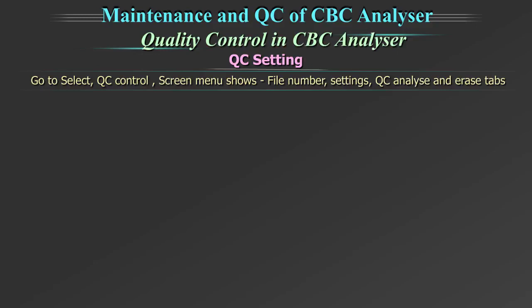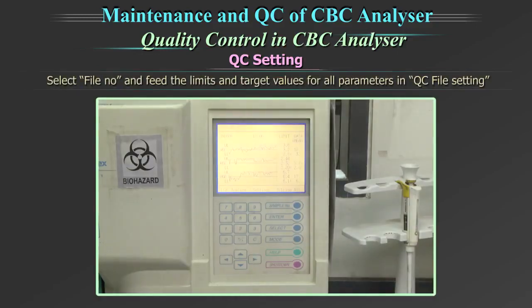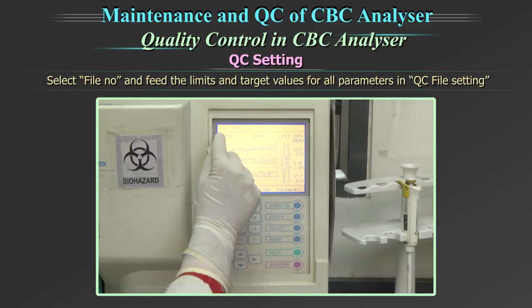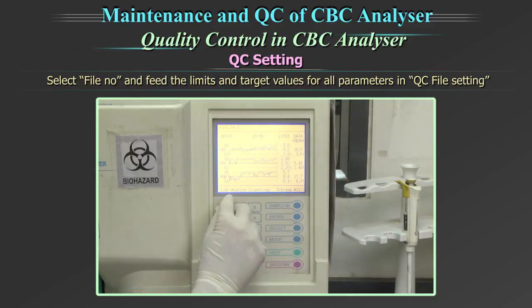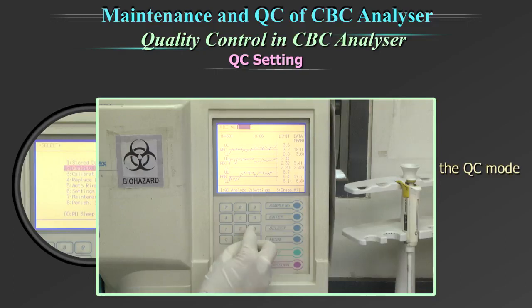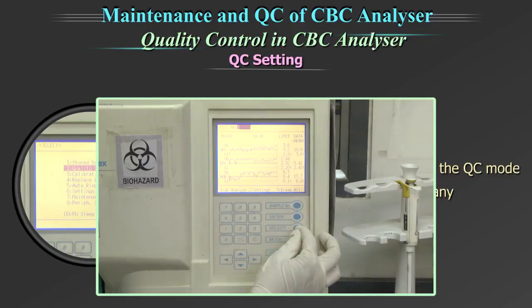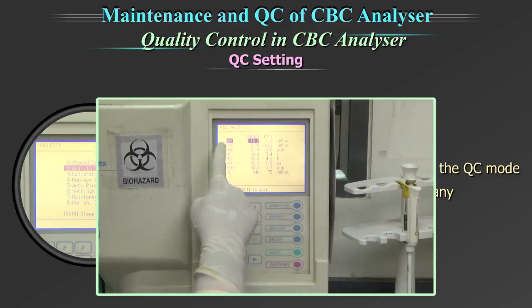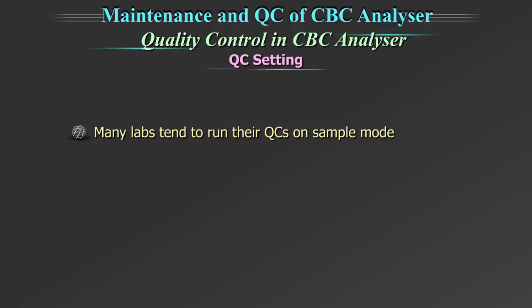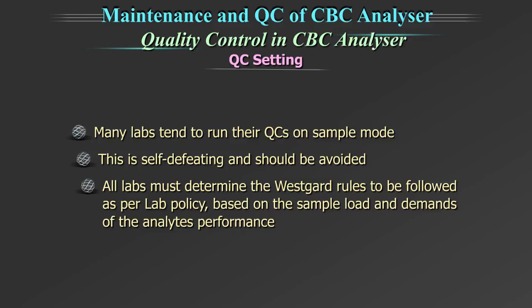and units. Go to Select, then Quality Control. The screen menu shows File Number, Setting, QC Analyze, and Erase tabs. Now select File Number and feed the limits and the target value for all the parameters in the QC file setting. There is a great advantage in running your quality control in the quality control mode. Since targets and ranges are defined, any outlier will immediately be flagged. Many labs tend to run their quality control on sample mode. This is self-defeating and should be avoided.